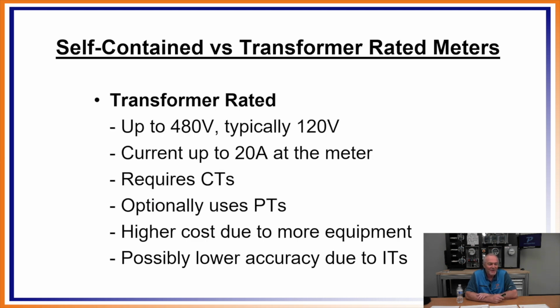So you've got self-contained versus transformer rated meters. With transformer rated, you can go up to 480 volt, typically 120 volt. Most of the meters you see out there now are multi-range meters, where you'll see on them, say, 120 to 480, so it can handle anything between 120 volts and 480 volts, and then current up to 20 amps at the meter. We know that because, as we've talked about previously, the test switch right there feeding the meter is rated 20 amps. So everything on a transformer rated site at the actual meter installation, the meter and the test switch, is all rated 20 amps.